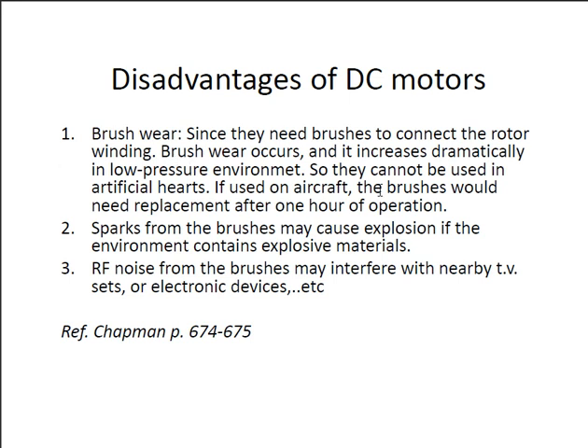Disadvantages of DC motors: brush wear occurs since they need brushes to connect the rotor winding, and this is increased dramatically in low-pressure environments, so they cannot be used in artificial hearts. If used on aircraft, the brushes would need replacement after one hour of operation. Sparks from the brushes can cause explosions with explosive materials nearby. Electrical noise from the brushes may interfere with nearby TV sets or electronic devices.